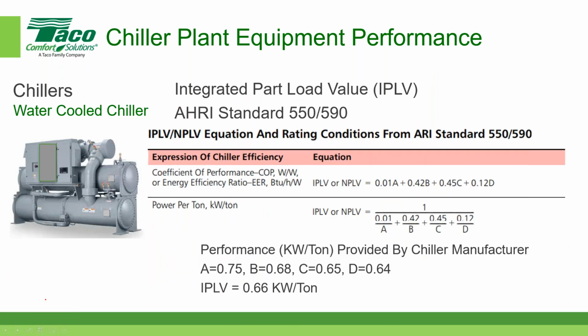And so the actual calculation looks like this. The IPLV is equal to that 0.01, saying 1% of the time it's operating at 100% load, 0.42 or 42% of the time it's operating at 75% load, at 50% load is 45% of the time, and 25% load is 12% of the time.